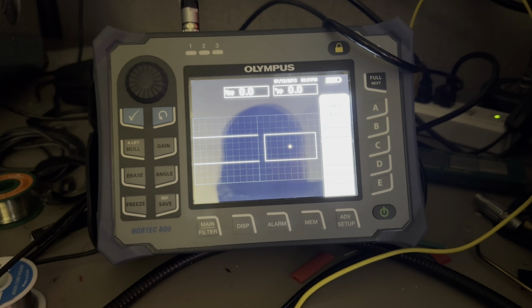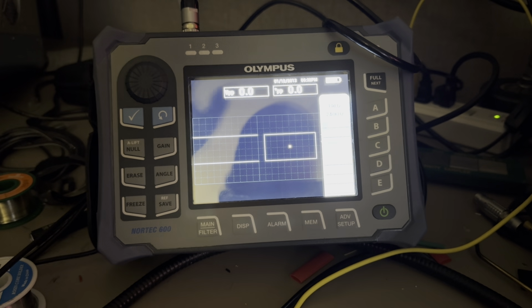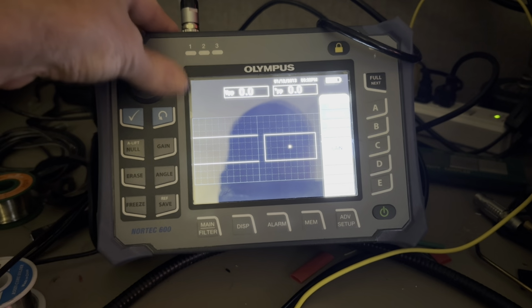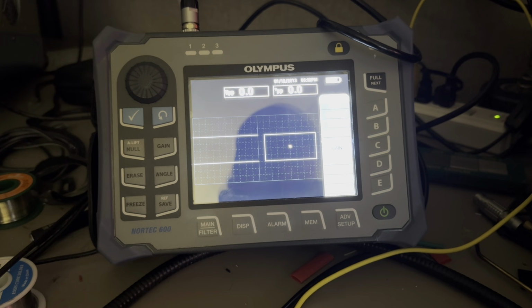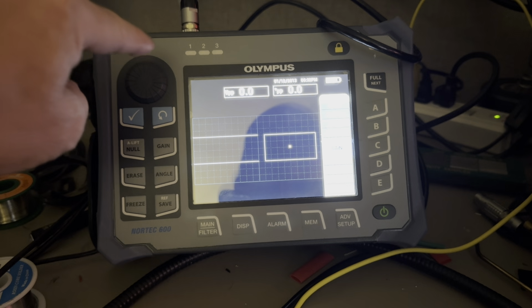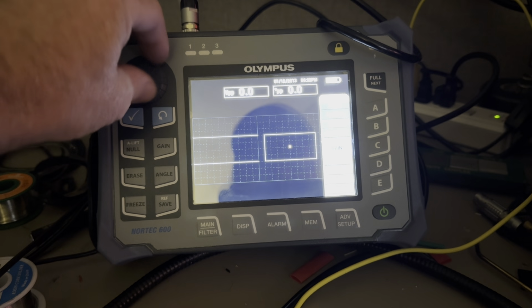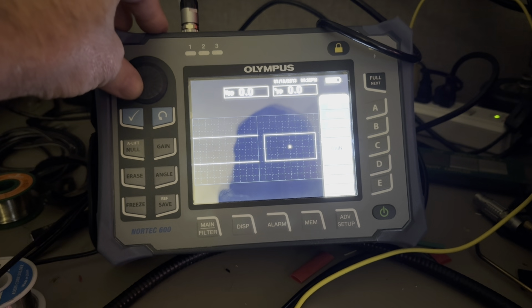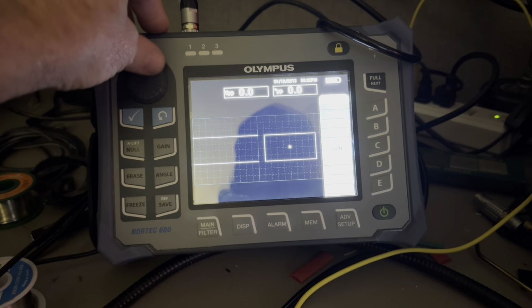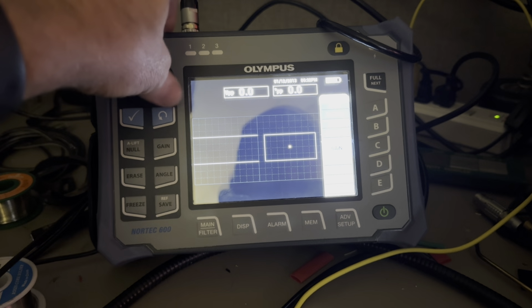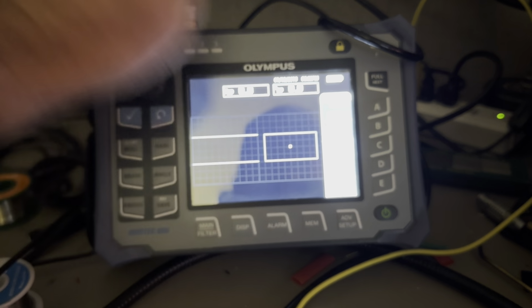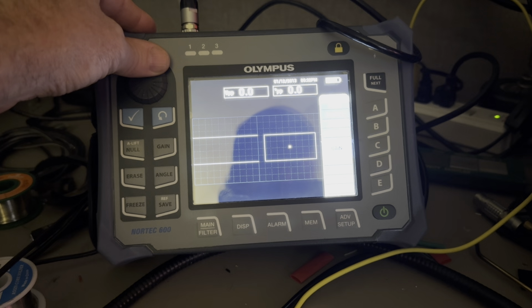Now, obviously my gain's super low because my impedance point is not moving too much. Also, it's dark in here, so I can't tell where my coil is, so I gotta rotate it manually here. Is it there? There we go. So that's going to be the side of my probe with the coil, right about there. But let's just crank some gain in here. Now, I've been playing around with my Nortec 500D this past week. And the smart knob's on the right side of the tester, which is also fine, but being right-handed, I like to handle the probe with my right hand and use the smart knob with my left hand. All right, so we're cranking the gain up. I forgot what we were doing there. So here's our gain values down here. All right, so we got some live probe action there. That's good.